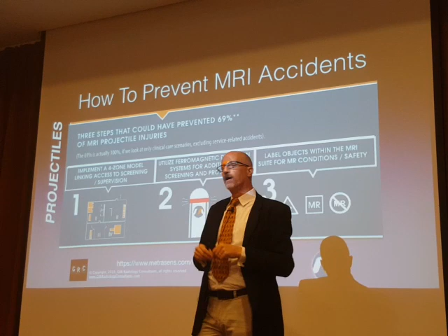Projectile objects, by definition, essentially have to be ferromagnetic. So if we use a ferromagnetic detection system to identify them before they go in the room, we can dramatically reduce the rates of those types of accidents. And the third recommendation here is to plainly, conspicuously label items that live in the MRI suite that have a likelihood of being brought into the room.